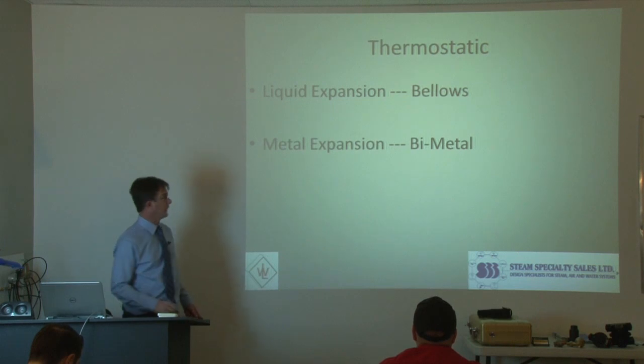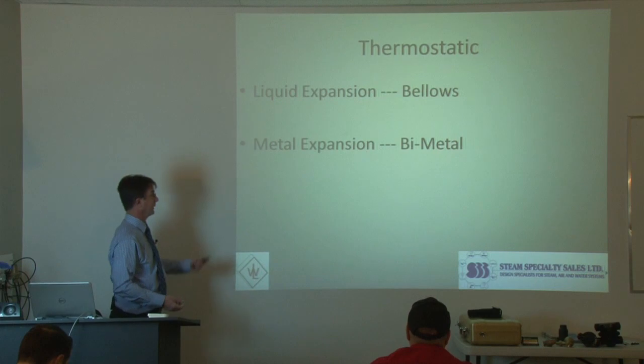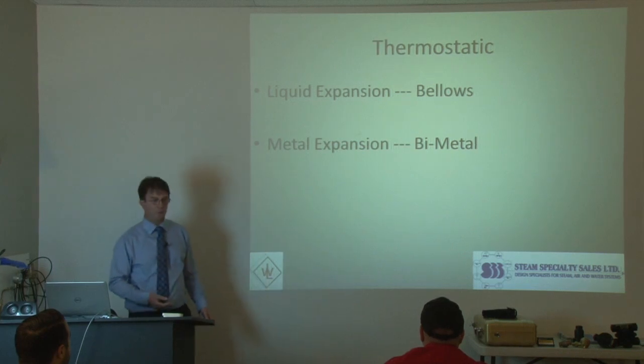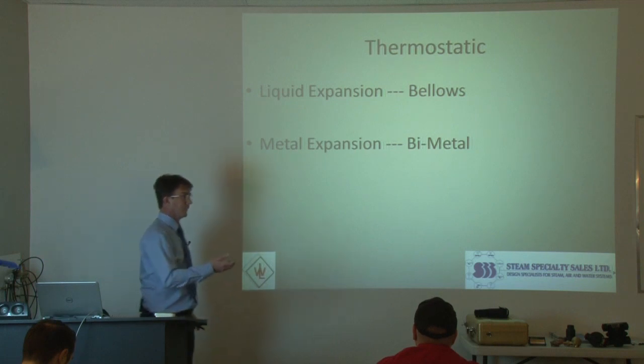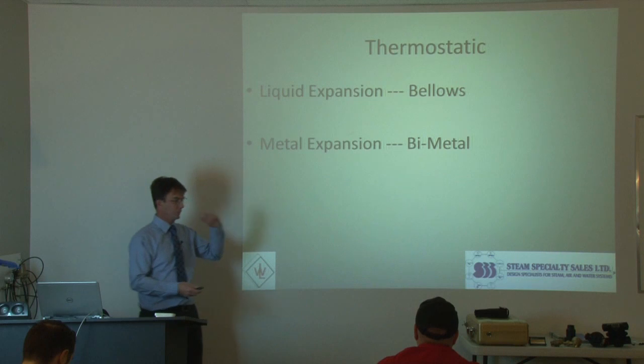There are two different types. Liquid expansion bellows, which is the one that we normally see in Canada. Metal expansion is bimetallic. I don't have an example of a bimetallic, but there are some out there. For example, Gestra, which is a brand name — a German company. They sell a lot of the bimetallic and like to promote those. You'll see them once in a while.